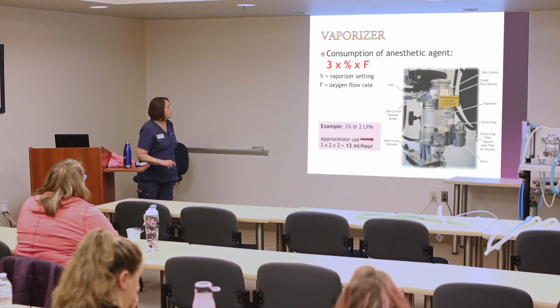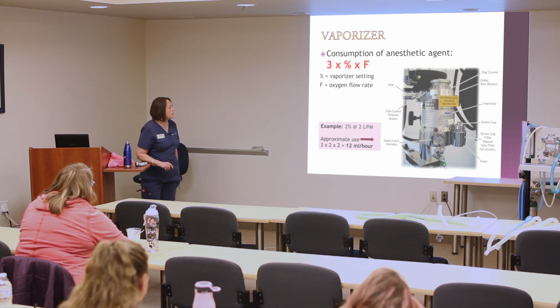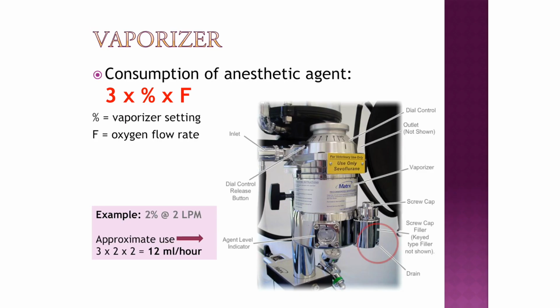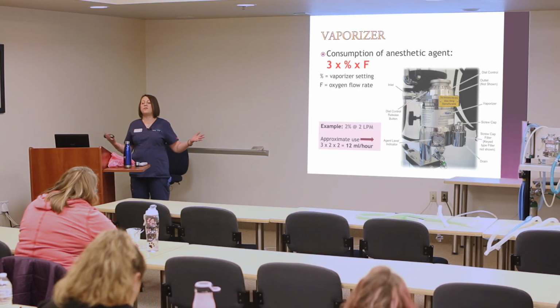And then as far as the vaporizers go, we do have a couple different types of vaporizers. Most of the time, on the bottom here, there's going to be a little hole. And that actually is where you would drain out your liquid anesthetic. Every now and then, the one in CT will start dripping liquid out of there, so that's not cool because that's actually isoflurane coming out of that hole.